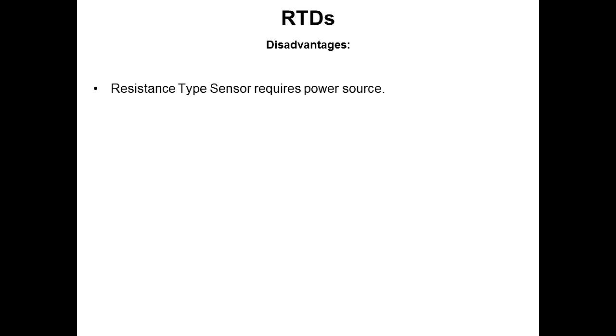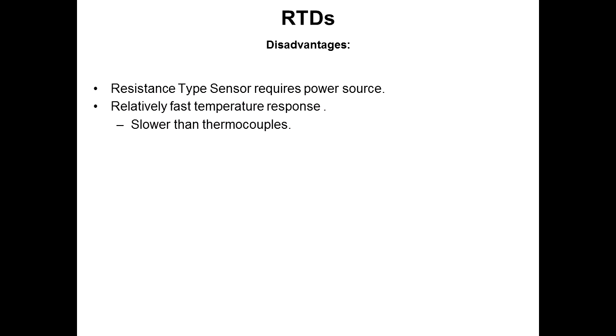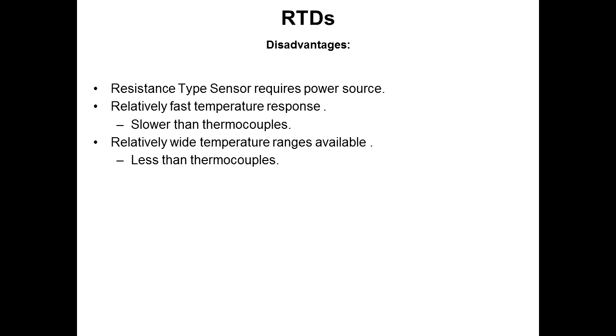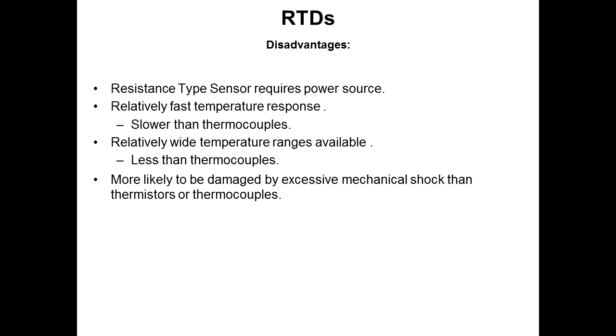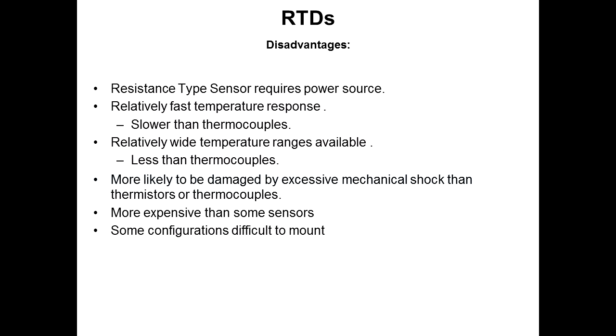Disadvantages: requires a power source versus a thermocouple. A relatively fast response, but much slower than a thermocouple because of the mass. Relatively wide temperature ranges available, but much less than a thermocouple. They're most likely to be damaged by excess mechanical shock, much more than a thermistor or a thermocouple. More expensive than other sensors. Some configurations are difficult to mount. They require a larger diameter probe to insert a sensor in, because you can't make them as small as you can a thermocouple. Some self-heating issues, especially at the higher resistance levels, and lead wire resistance issues are a big problem.